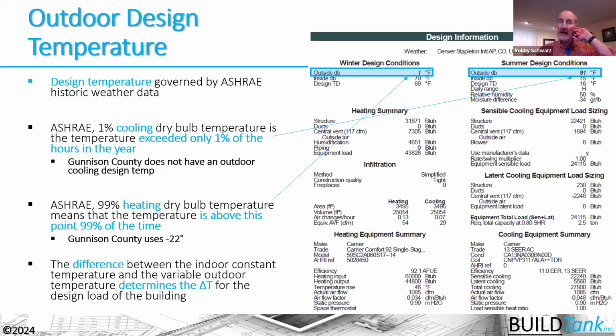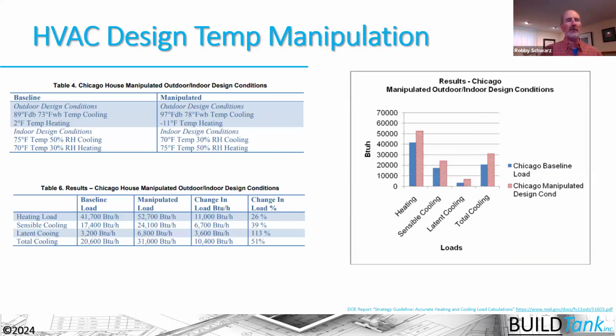So these are things that we need to look at and ensure that they've been entered properly, because if they aren't entered properly, we can affect the design load. We can undersize or oversize our equipment. And remember, our goal is to ultimately properly size there. So a group called IBACOS, which is a building science consulting and research firm based out of Pittsburgh, did some studies here, and they basically saw that if people manipulated the data that was entered into a Manual J, they're going to affect the loads pretty directly.